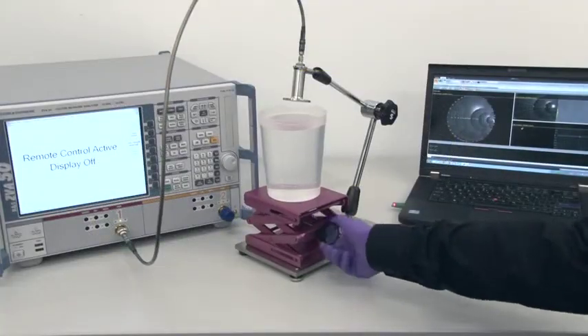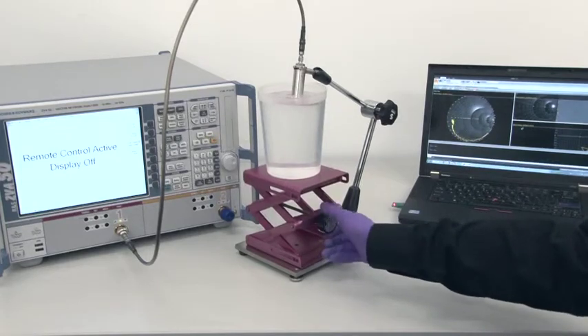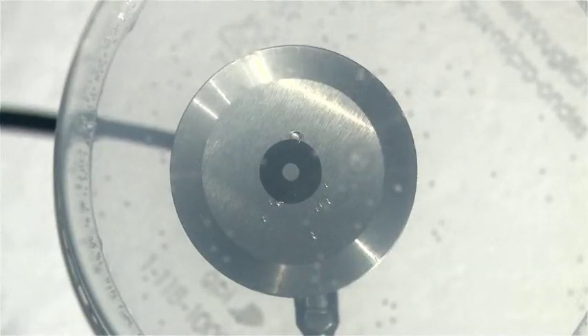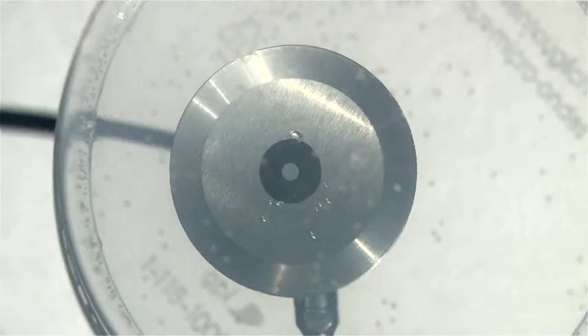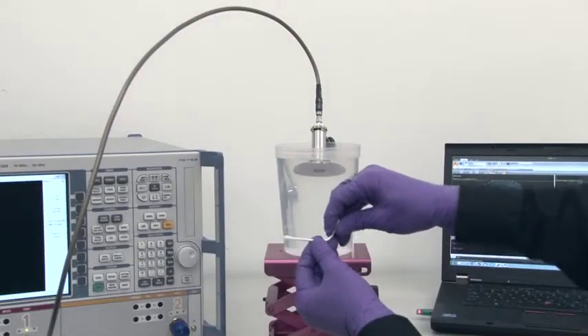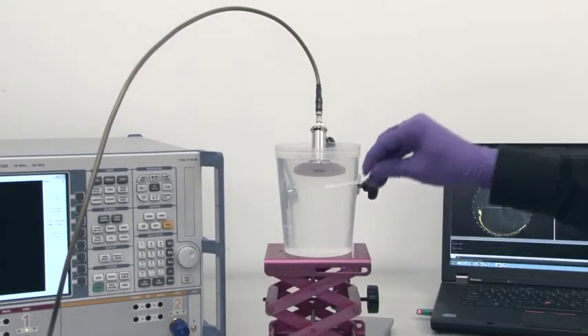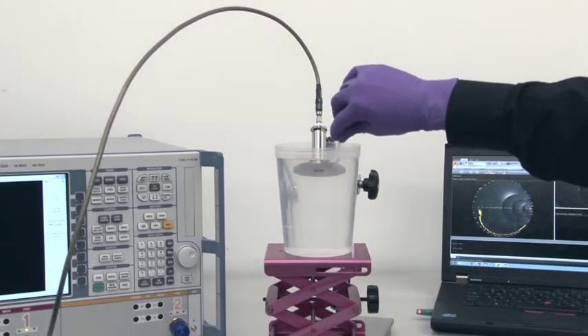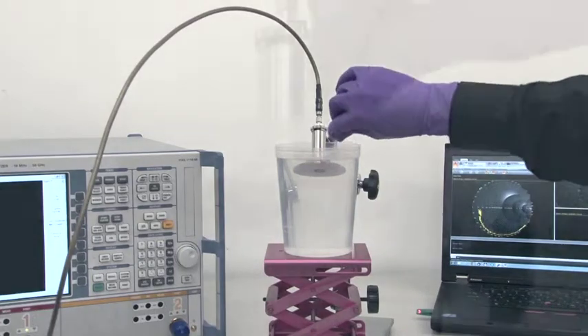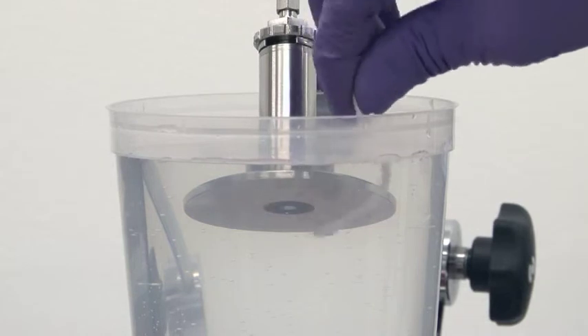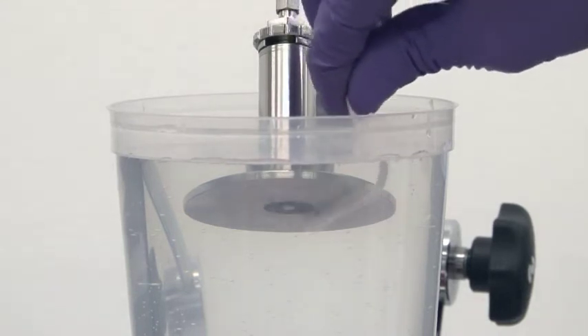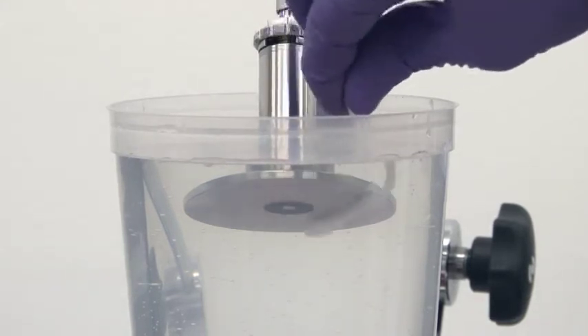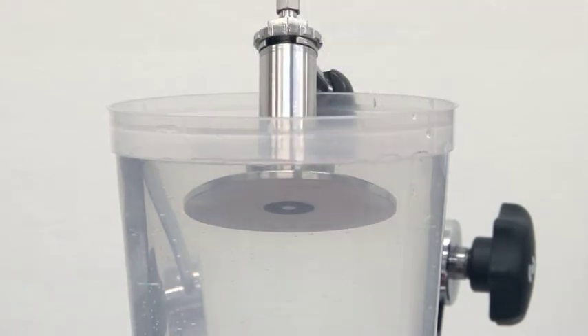Lift the liquid to the probe. It can happen that air bubbles form on the probe surface. Use soft and inert material like cotton swab to remove the air bubbles. The size of potential air bubbles can be very small, below the visible sizes. It is a good measurement practice to clean the probe surface after immersion.